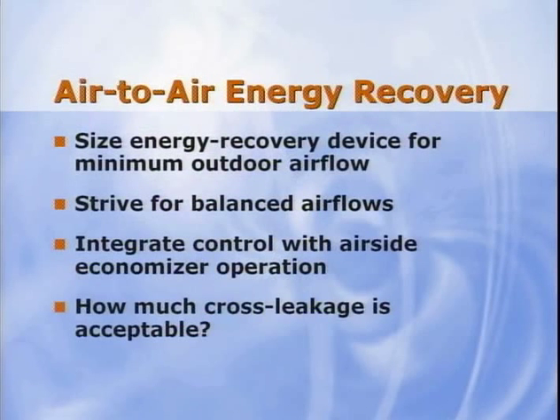When the economizer is activated, air-to-air energy recovery offers no benefit. In fact, unless the wheel is turned off, it actually increases the cooling load by adding heat to the entering outdoor air. Achieving maximum energy savings depends on proper economizer operation and integration of energy recovery into control of the entire system. Next, decide how much cross leakage is acceptable. In a mixed air system, cross leakage between the exhaust and outdoor air streams is seldom a problem. Most of the air that returns from the space is recirculated as supply air anyway. For most applications, the amount of leakage is usually less than 5%.